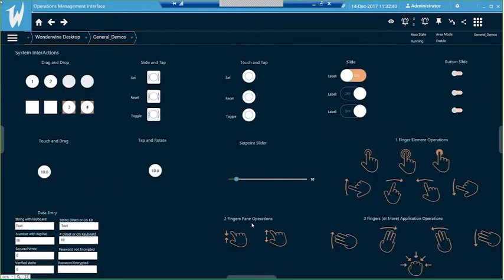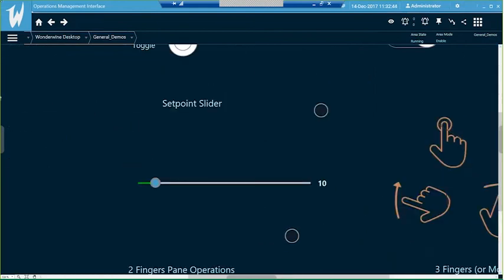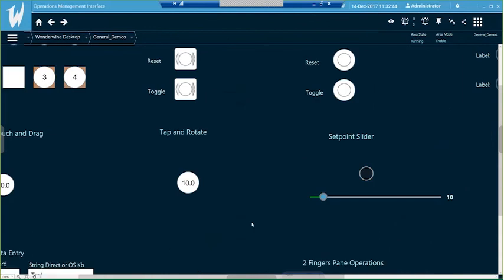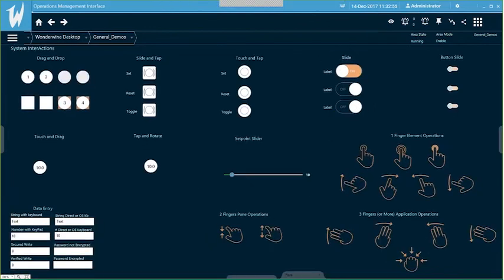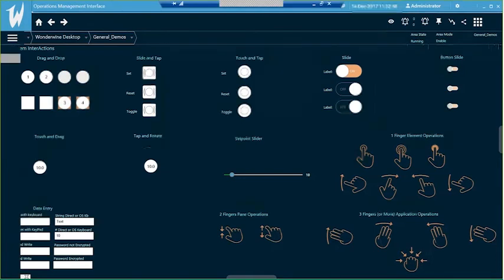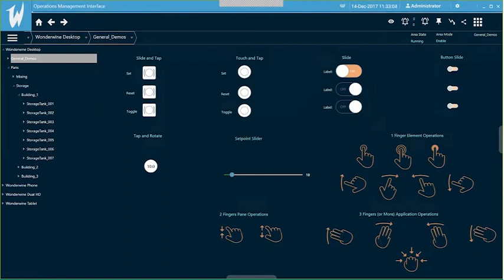Pan and zoom is a two-finger operation. Double-click takes it back to a regular view. Three-finger operations bring up menus, including the navigation model. If you build a plant model in System Platform, it automatically propagates to the viewer — nothing to set up. You attach graphics to assets — automation objects that can be devices, units, or areas. Once graphics are linked, there's no additional work within the OMI application — everything is automatically linked and the system knows your selected asset.